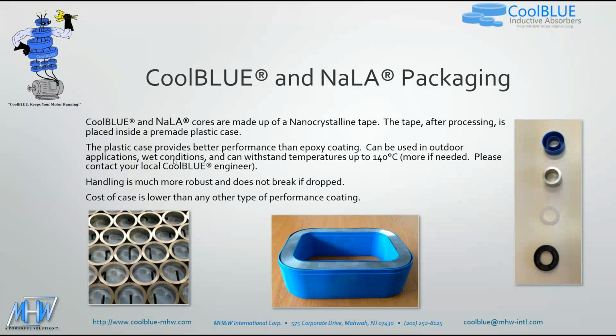That can be used in outdoor applications, wet conditions. They can withstand temperatures up to 140 C. Handling is much more robust, and they typically do not break if dropped. And the cost of putting them inside this plastic case is lower than any other type of coating, especially epoxy.